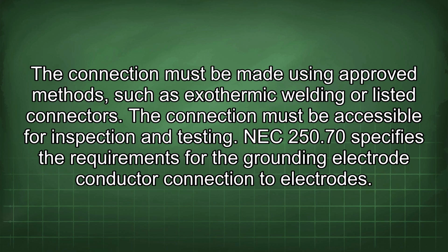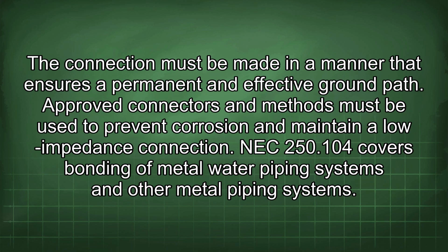NEC 250.70 specifies the requirements for the grounding electrode conductor connection to electrodes. The connection must be made in a manner that ensures a permanent and effective ground path. Approved connectors and methods must be used to prevent corrosion and maintain a low impedance connection.